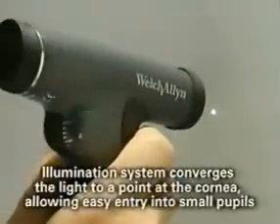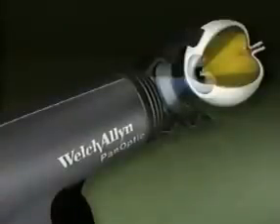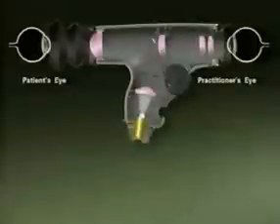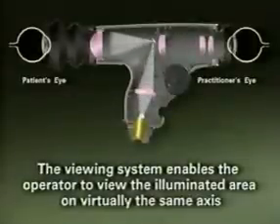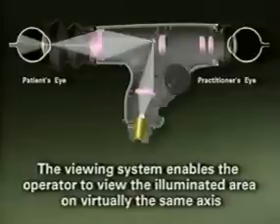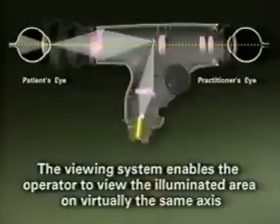Welch Allyn's patented new axial point source technology converges the bright white halogen HPX illumination to a point at the cornea, allowing easy entry into even the smallest pupils. Then, axial point source optics enables the illumination pathway to diverge to the retina, creating a very wide illuminated area of the fundus. Simultaneously, the scope's unique viewing system allows the operator to view the illuminated area on virtually the same axis, creating the widest field of view attainable in undilated ophthalmoscopy. The practitioner is actually viewing the fundus while looking through the mirror, which directs the illumination into the eye, maximizing the alignment of the viewing axis with the illuminated area.